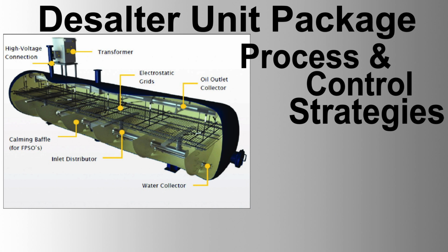1. Feed-forward control from separator to desalter. Flow meter at separator outlet, FT-SET 301, measures the flow rate and composition of the outlet streams. Feed-forward signal to desalter inlet valve, FVS 101, adjusts the inlet flow rate to the desalter based on the separated phases. 2. Feedback control within separator, level transmitter for oil-water interface, LT401, and pressure transmitter, PT501, maintain optimal interface levels and pressure to ensure efficient separation.